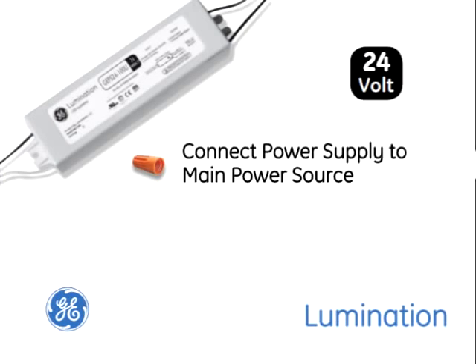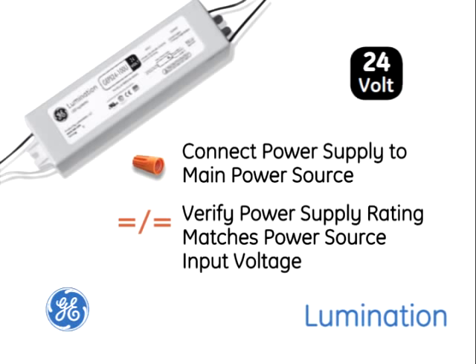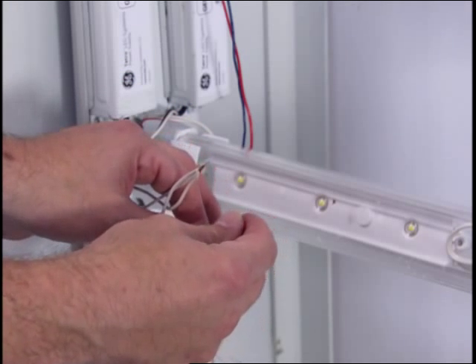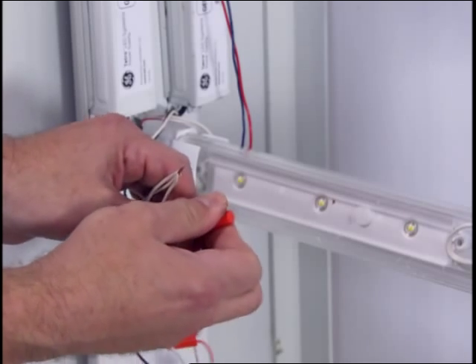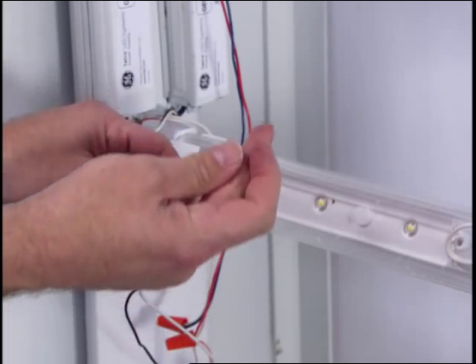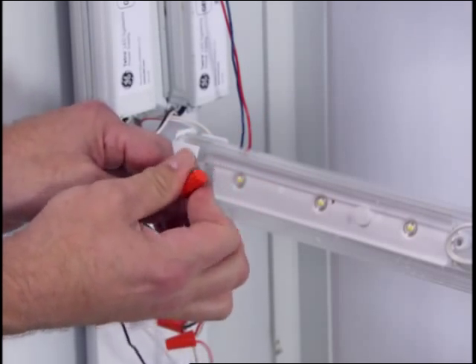Now connect the power supply to the main power source. Verify that the power supply rating matches the power source input voltage. Connect the black AC line to the black input wire of the power supply. Connect the white neutral line to the white wire of the power supply.